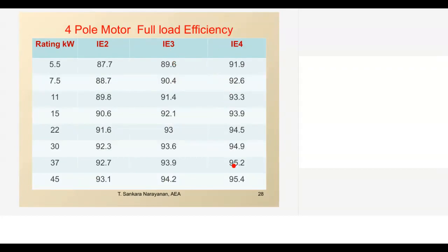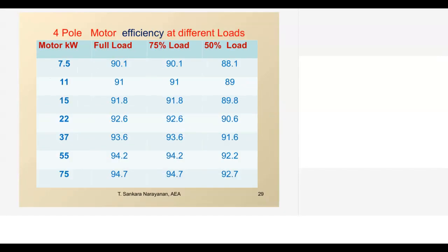IE4 is a reluctance motor. Today only some of the OEMs are offering it, so we have to wait for the overall performance of IE4 and see where we can shift. Otherwise, IE3 can be provided if the motor operating hours are higher. Then again, within this motor, how the load matters. If we see a 7.5 kilowatt motor, the full load efficiency is 90%, and at 75% load it maintains the same. But when the load drops to 50%, the efficiency drop is around 2%.